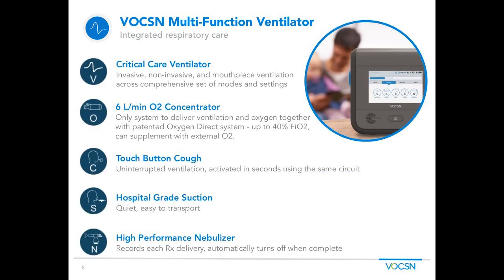So what exactly is VOCSN? First and foremost, VOCSN is a critical care ventilator. It does invasive, non-invasive, and mouthpiece ventilation across a comprehensive set of modes and settings. All of the modes and settings you're used to using today with any mechanical ventilation, VOCSN is going to be able to do, again across invasive, non-invasive, and mouthpiece ventilation. It also has on board a 6 liter per minute oxygen concentrator. This is the only system in the world to combine ventilation and oxygen into one single breath for the patient, delivering that pure oxygen on the front end of the breath, for very efficient and effective delivery of oxygen.